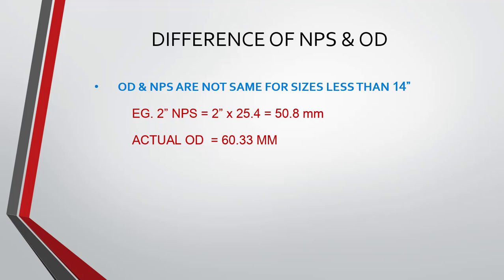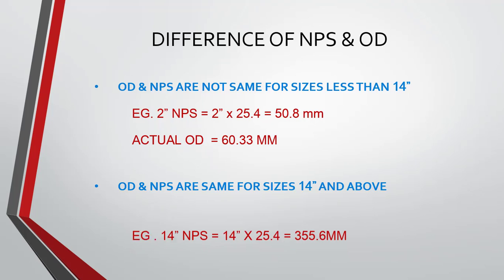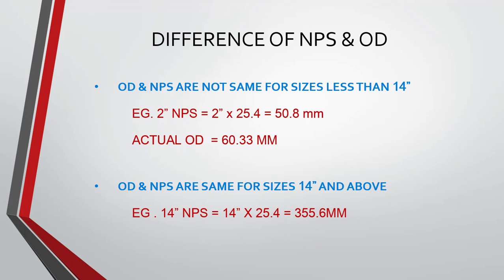For sizes 14 inches and above, OD and NPS are the same. For example, 14 inch NPS converted to metric units is 355.6 mm, and the actual OD of a 14 inch pipe available in the market is also 355.6 mm. This is the unique difference between NPS and OD. Technically, NPS is the term referred to in order to identify the piping size — you can call it pipe size or piping size; it doesn't matter.